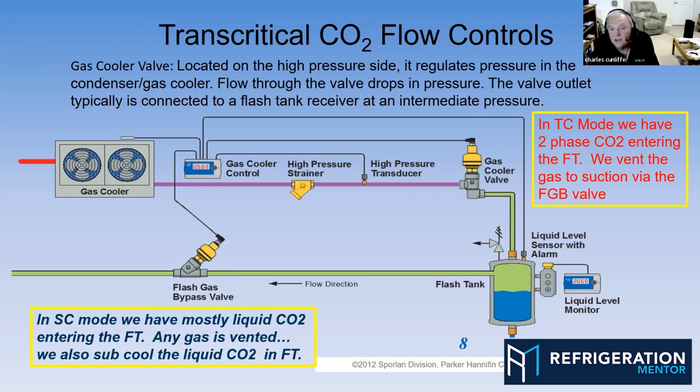Absolutely. And Brett, that's why I said earlier that you have to be mindful of your piping because even at best engineering attempts that you make, there are times where the subcooling is just barely there, right? I'm sure you guys have seen that. And again, if you have piping where you're picking up a lot of heat, I mean, some of the stores that I've been involved in, ye gods, the run going out to the front of the store is hundreds and hundreds of feet. So I remember early on where some stores weren't really as careful with the piping.